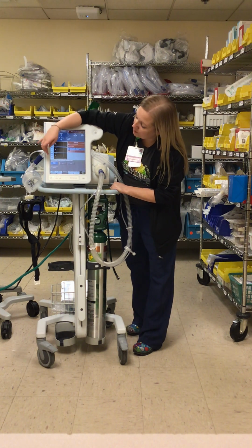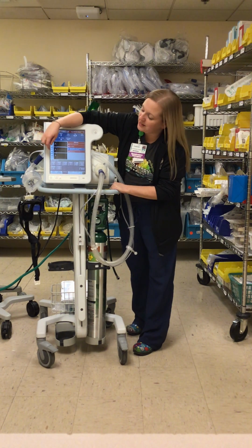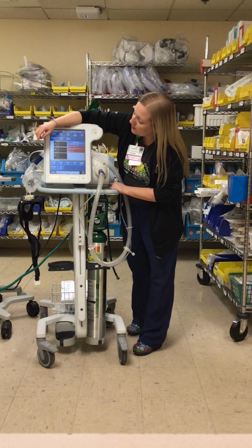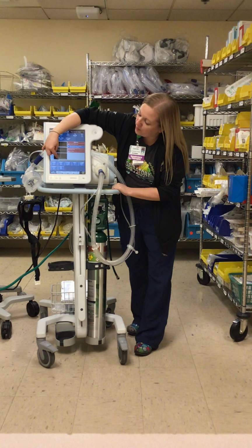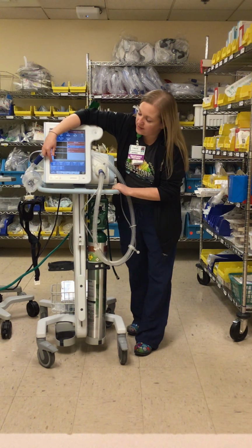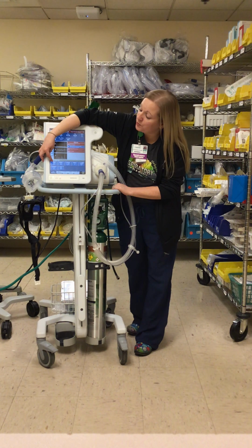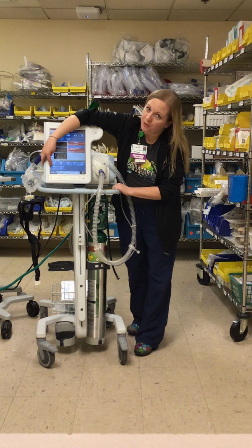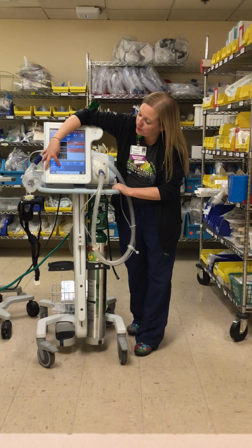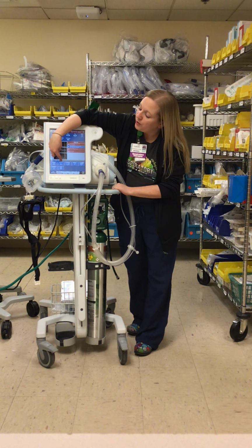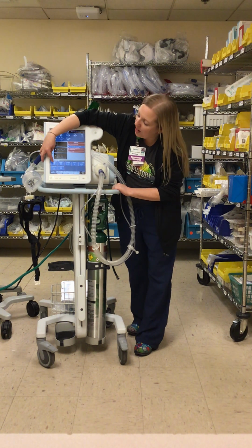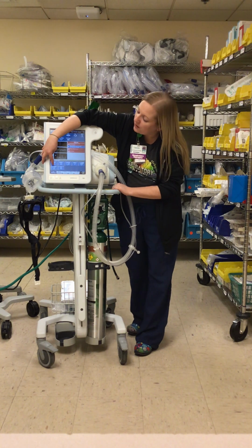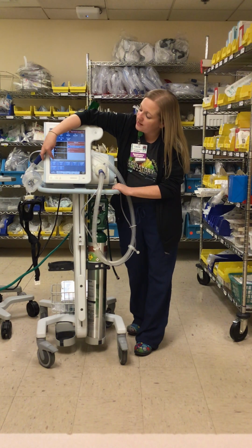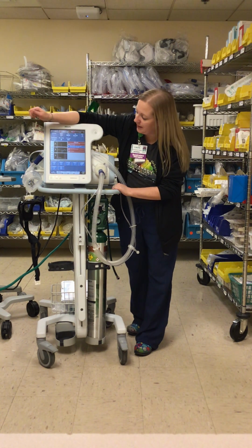One of the other modes you'll see the most is BiPAP, which on here is called ST, which stands for spontaneous time. Same thing, the gray bar, it says active mode ST. And then you have different settings. Your first one is your IPAP, which is your inspiratory pressure. You have your EPAP, which is your expiratory pressure, and your FiO2, and a backup rate. So if the doctor asks what your patient is on, you give them the settings as I over E, so IPAP over EPAP. So 15/8, oxygen's 50%, and their backup respiratory rate is 15. So that's how you tell the mode and the settings on the V60.